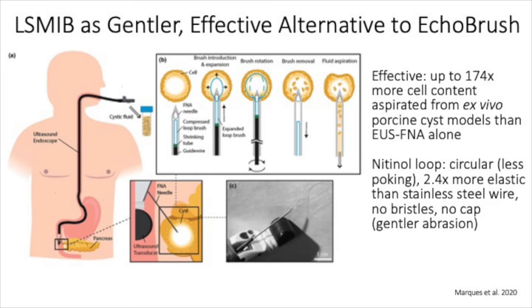So what that means in the context of the LSMIB is that when the brush loop wire is inside of the needle before deployment into the cyst, it is flexible and compressed. But when the wire enters the warmer environment of the cystic cavity, it springs back into a circular shape and conforms to the spheroidal shape of the cystic cavity. Not only does the nitinol wire have a useful shape, but it is almost 2.5 times more elastic than stainless steel wire, which is the industry standard for cytologic brushes, making it a gentler alternative.